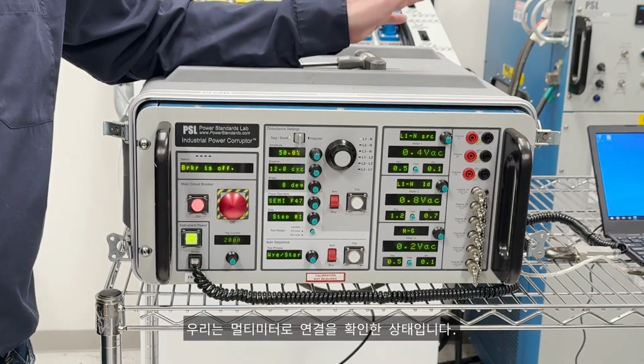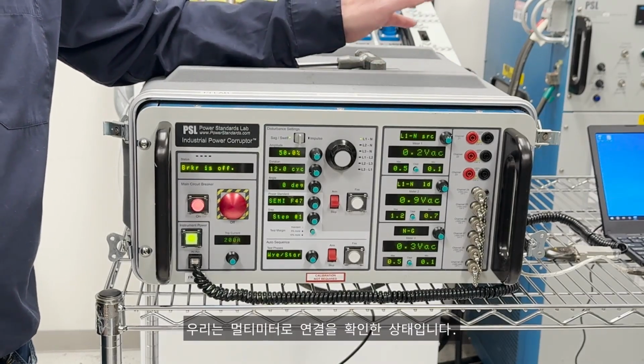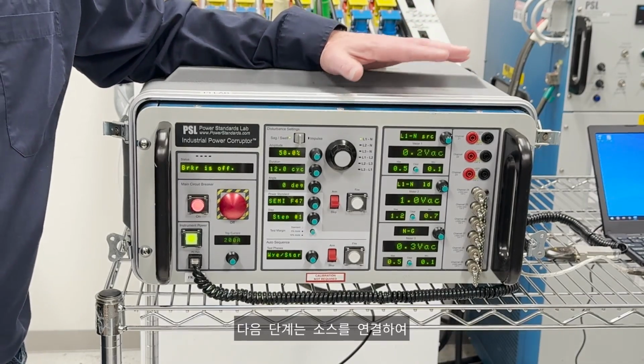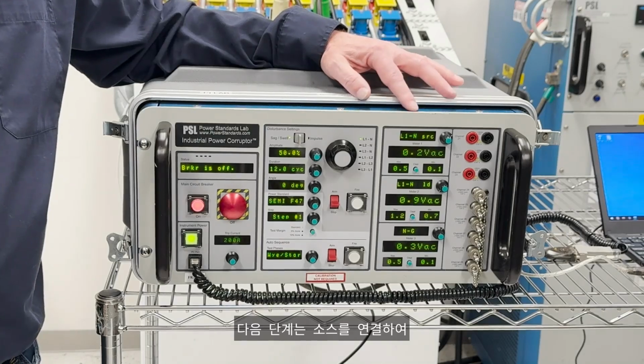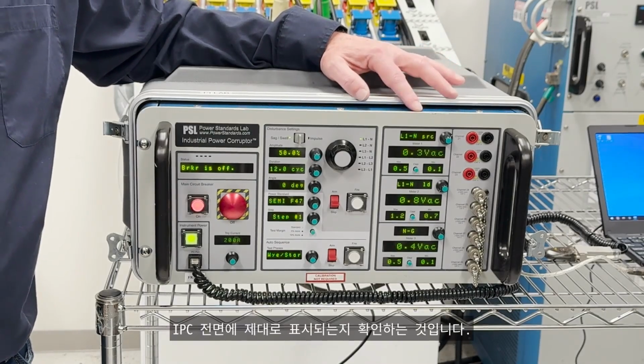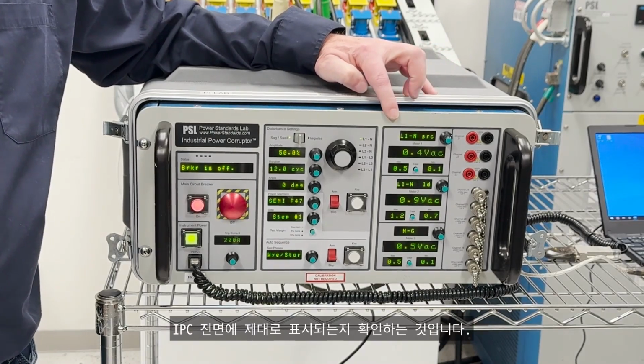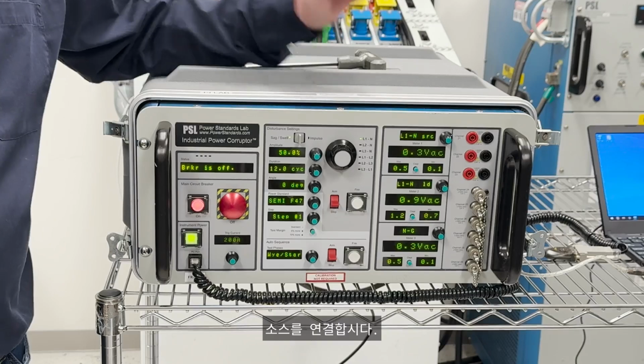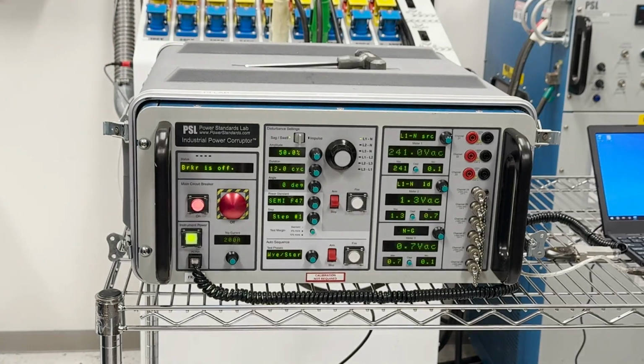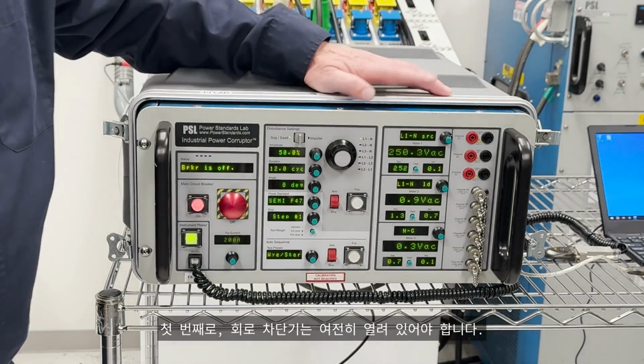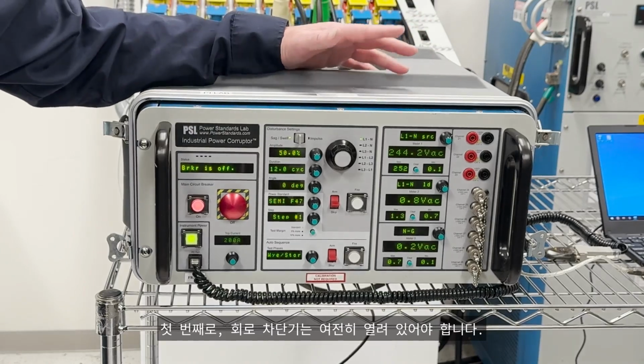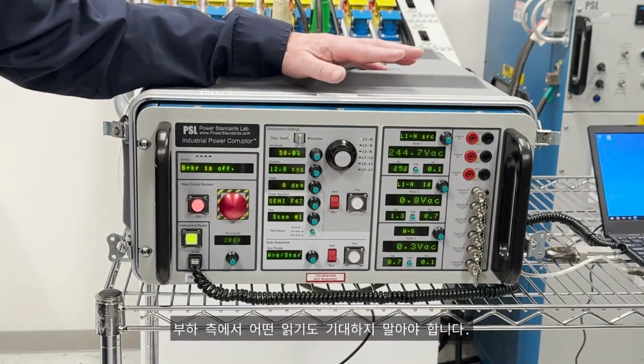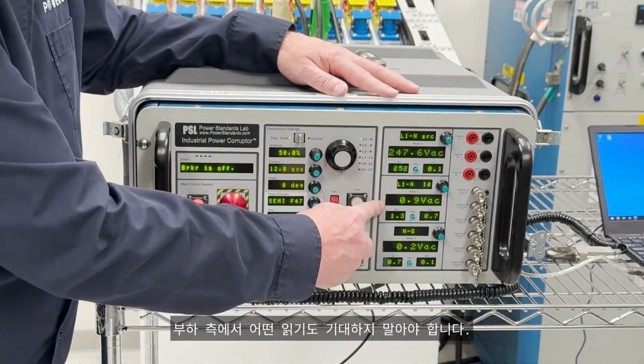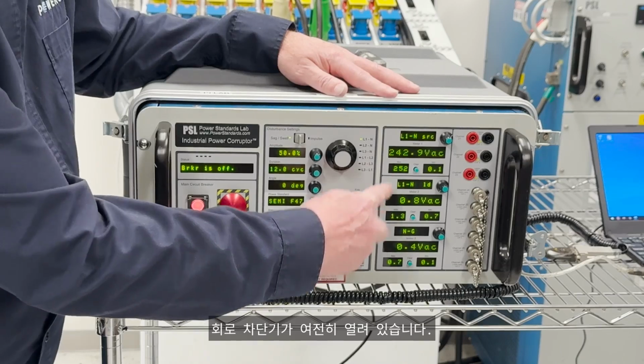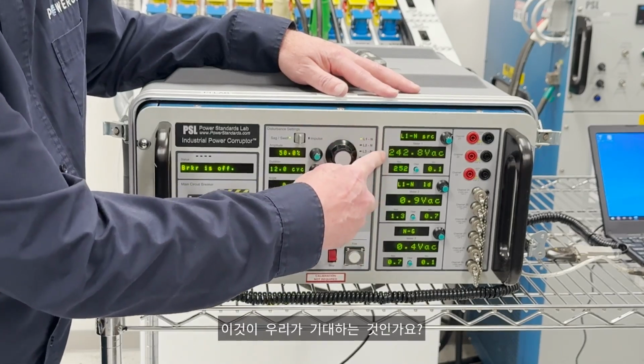We've verified the connections with the multimeter. The next step we'll take is to connect the source and verify that it is properly reflected on the front of the IPC. So with that, let's connect the source. Now, first thing, circuit breaker should still be open, so we should not expect to see any reading on the load side. Circuit breaker still open, but on the load side, is this what we expect?